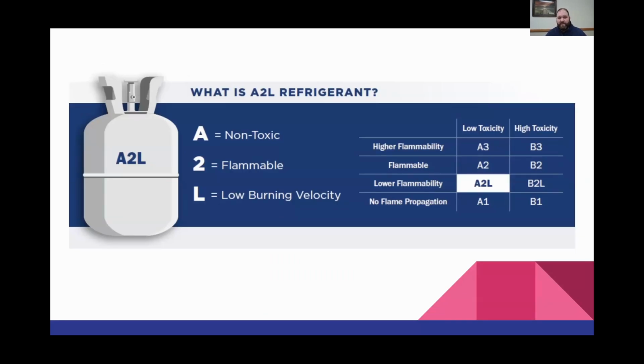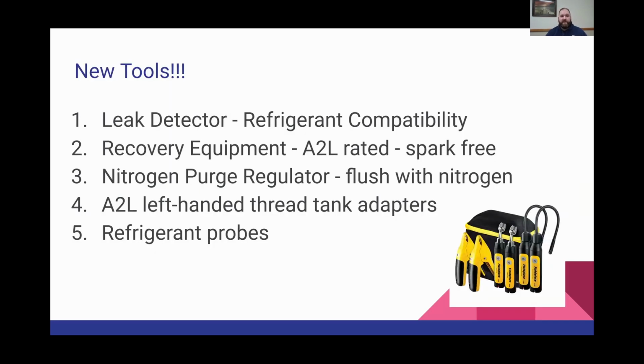What is an A2L? An A2L is an A, non-toxic, two, flammable, but they added this L designation because it has a low burning velocity, meaning if it catches on fire and you remove the flame from it, it will not continue to burn on its own. So are they flammable? Yes. Is it flammable like an A3? No. So there are some additional considerations we need to take when talking about A2L refrigerants.